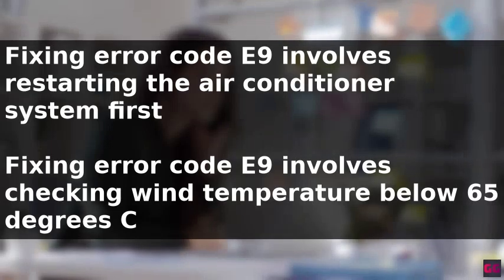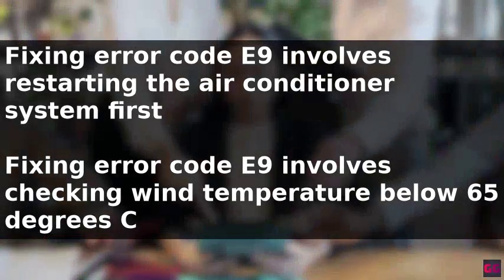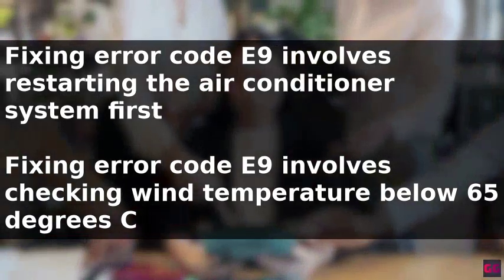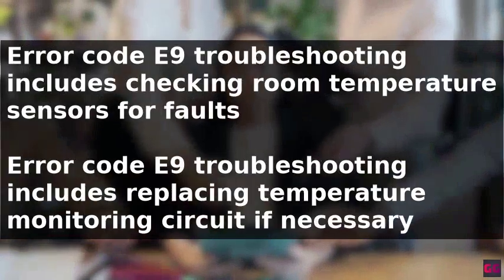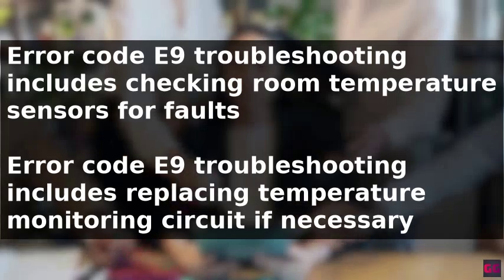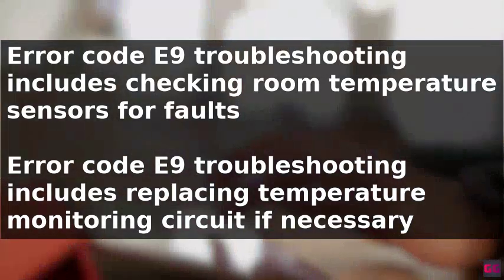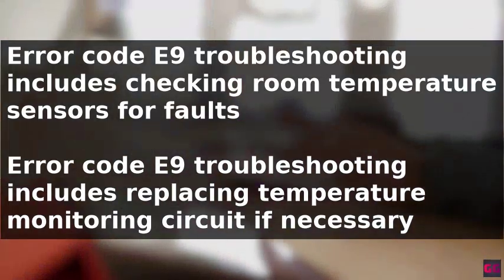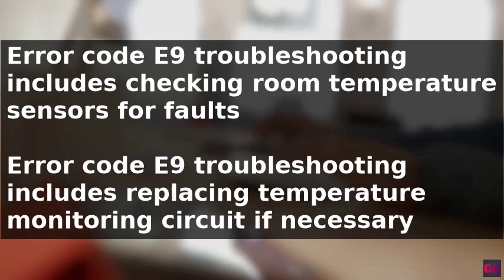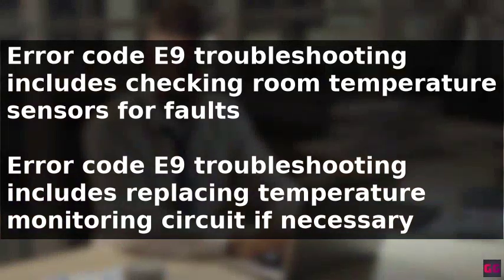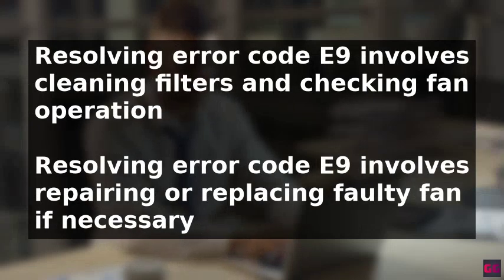Start by restarting the air conditioner system through power cycling and confirm that the wind temperature is below 65 degrees Celsius. If the error persists after the system has run for some time, check the room temperature and pipe temperature sensors for faults, and repair or replace them as necessary. If the sensors are functioning properly, replace the temperature monitoring circuit on the indoor unit.